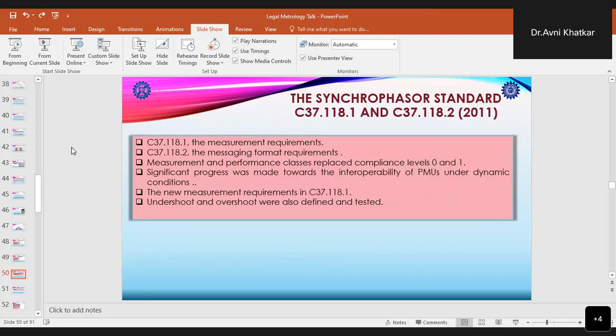So in 2011, this 2005 standard was split to form two different standards, that is IEEE C37.118.1 and C37.118.2. The C37.118.1 standard formed the measurement standard, whereas the .2 standard became the communication standard. In the measurement standard, the measurement and performance classes were included, and these performance classes replaced the earlier compliance levels, that is level 0 and level 1.